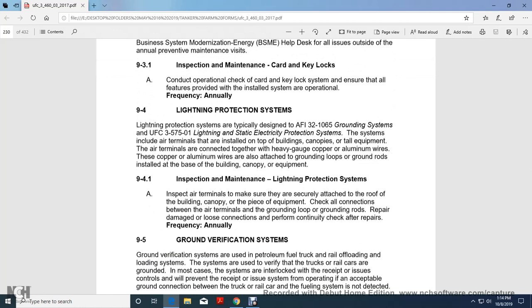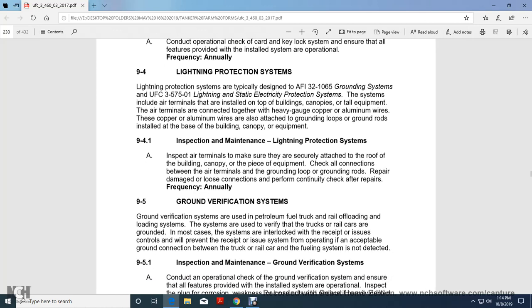Alright, 9.4, Lightning protection system. The lightning protection system is designed in accordance with AFI 32-1065, Grounding Systems, and UFC 3-575-01, Lightning and Static Electricity Protection Systems. These systems include air terminals installed on the building, canopy, and tall equipment. The air terminals are connected together with heavy gauge copper or aluminum wires, which are attached to ground loops and ground rods installed at the base of the building, canopy, or equipment.